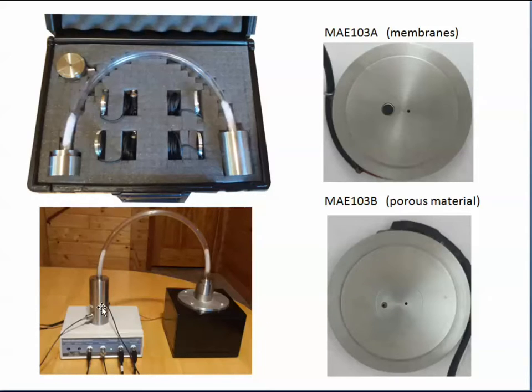The actual sample holder for the 103s is here, where this cable is leading to. The bottom of the stack up has a microphone embedded in this steel body. So here's the microphone base with the microphone embedded in it, the flexible tube, and here's the coupler that goes to the microphone base, and this end goes on top of the speaker driver.